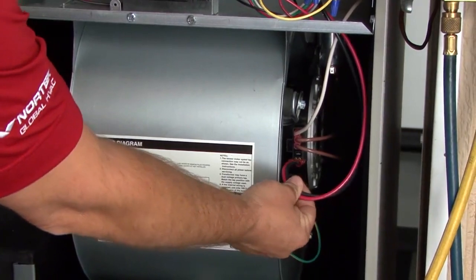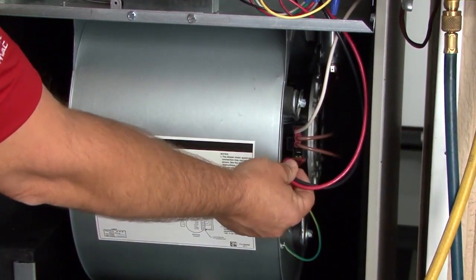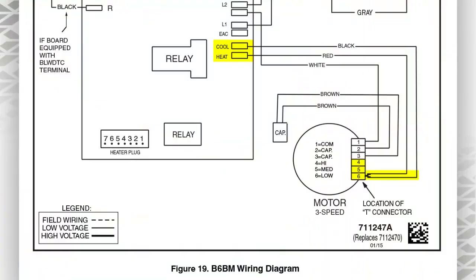So this is just a standard PSC motor. And like I said, again, your motor speed selections are done on the motor itself by moving the wires to the appropriate terminals. You've got a 3-speed motor. 4, 5, and 6 are the terminals, as you will see from the wiring diagram.